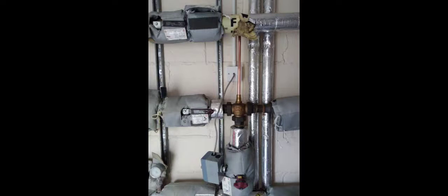And as you know, underfloor heating shouldn't be at any temperature. There are certain temperatures you should have the flow rate at, as you can start getting cracks and stuff in floors if you're getting 80 Celsius or above for underfloor heating, when it's only maybe designed to be at 50 or 60. So anyways, I connected this up.